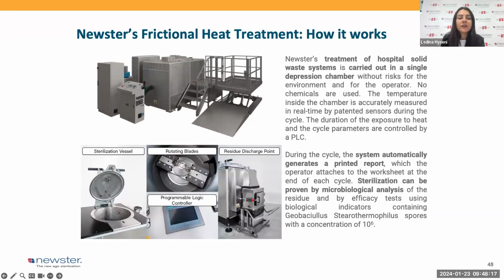Here I'd like to briefly summarize how the frictional heat treatment works. The treatment is carried out in a single depression chamber without risk for the environment and for the operator. No chemicals are used during the cycle. The temperature inside the chamber is measured in real time by patented sensors, and the duration of the exposure to heat and the cycle parameters are controlled by the PLC. During the cycle, the system automatically generates a printed report which the operator can attach to the worksheet at the end of the cycle. The sterilization can be proven, of course, by microbiological analysis and by efficacy tests using biological indicators.